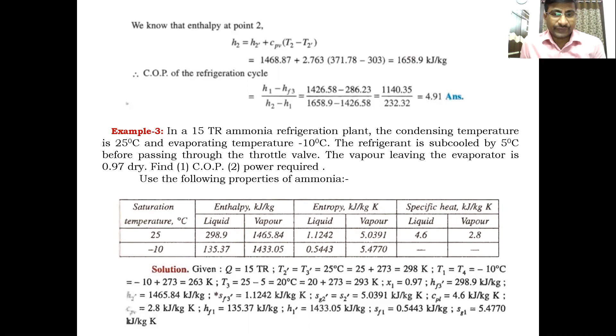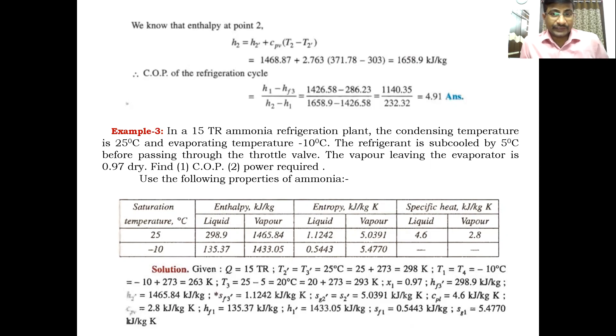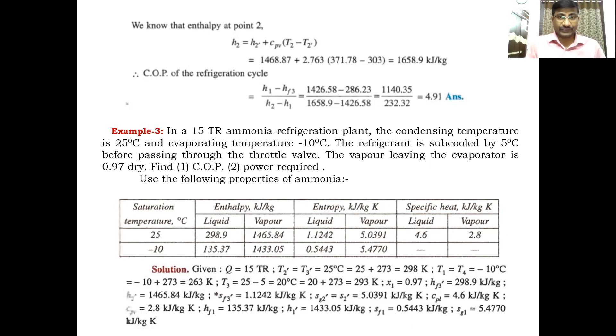What are the advantages of subcooling? Subcooling has a major effect on the COP — it is the major factor affecting the performance of the VCR system. Whenever subcooling occurs, it increases the refrigeration effect without changing the work input, thereby increasing the COP. Due to subcooling, after expansion the liquid part is more than the vapour part, and that liquid part is very useful in the evaporator to absorb heat and increase the refrigeration effect.